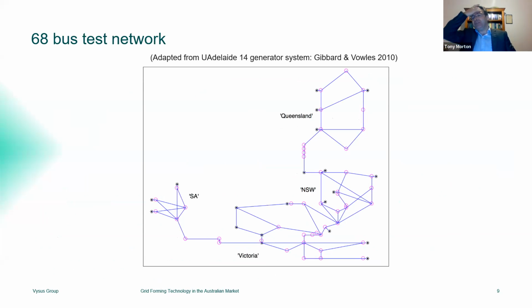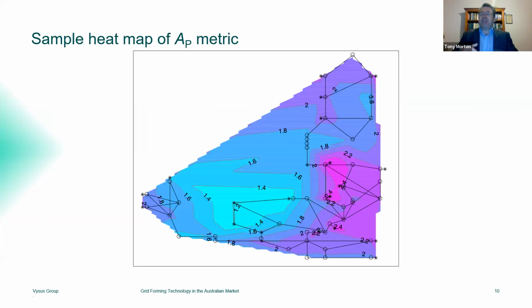we've done this exercise using a very simplified picture of the Australian NEM, the power system. So this is a 68 bus test network that's just abstracted from a very broad brush picture of the Australian system. So these are just labels for different Australian states and the interconnections between them. And we can actually then do this basic power flow analysis and get a kind of heat map of these sensitivity coefficients. So this is the angle active power sensitivity. So one of those 4 sensitivity coefficients that we can derive from doing some basic incremental power flows. And we see that it does pick out the particularly strong and weak areas of the network. We see in particular, there's one particular area of the Australian system called West Murray that's known to be particularly weak. And we see that reflected when we do the sensitivity calculation.